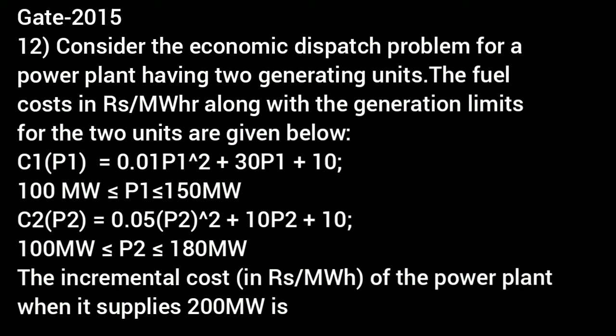Given that P1 plus P2 is equal to 200 megawatt, let it be equation 1. dC1 divided by dP1 is equal to 0.02 P1 plus 30 and dC2 divided by dP2 is equal to 0.10 P2 plus 10. So dC1 divided by dP1 is equal to dC2 divided by dP2, that is 0.02 P1 plus 20 is equal to 0.10 P2, and P1 is equal to 200 minus P2. Let it be equation 2. We get P1 is equal to 0 megawatt and P2 is equal to 200 megawatt. The limit of P1 is 100 megawatt to 150 megawatt and the limit of P2 is 100 megawatt to 180 megawatt. So we can't take P2 is equal to 200 megawatt and P1 is equal to 0 megawatt.